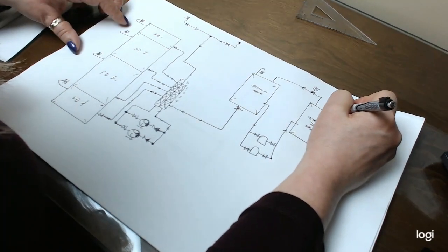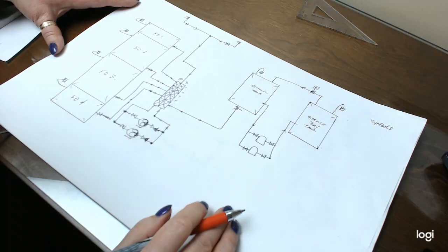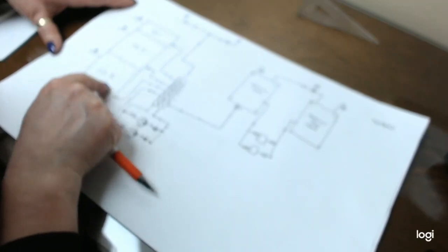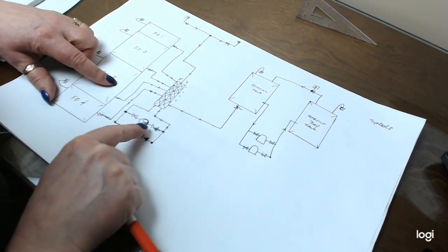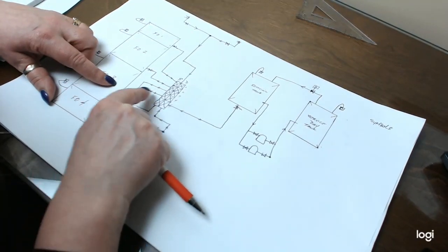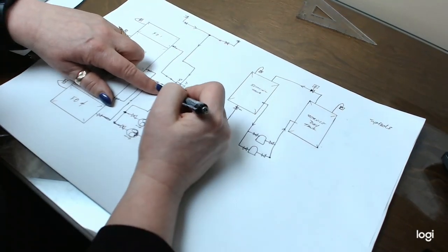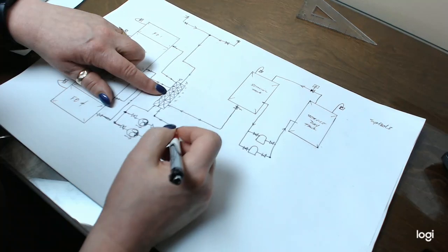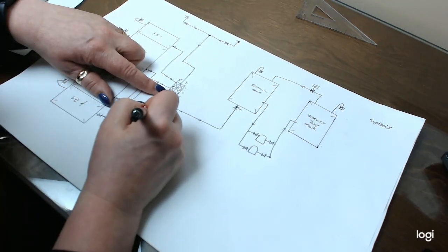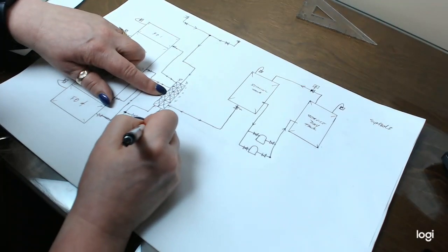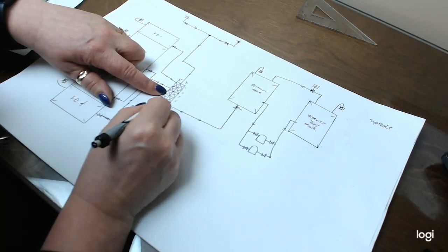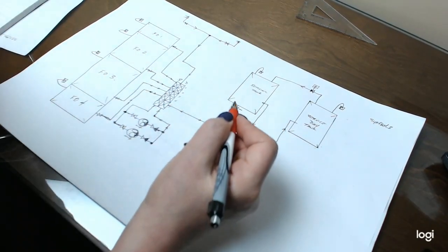Okay, so now we've got all the bits and pieces together. We've got our direction and how everything is flowing. So I want you to get an idea that if I wanted to take fuel from this tank and move it into the settling tank, I could open this valve here on the suction side of this tank. One of the pumps would be turned on. The pump would take fuel from this side of the manifold, move it up in this direction, move it into this manifold, and then eventually put it into the settling tank.